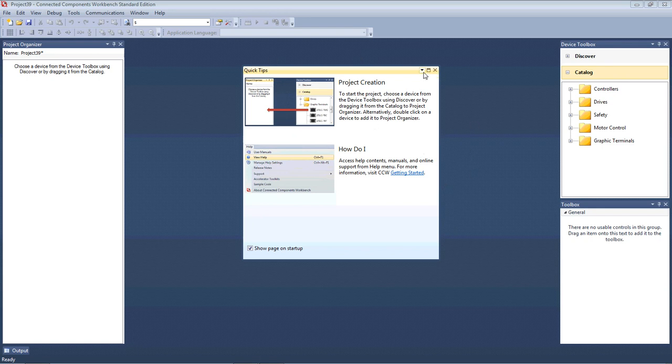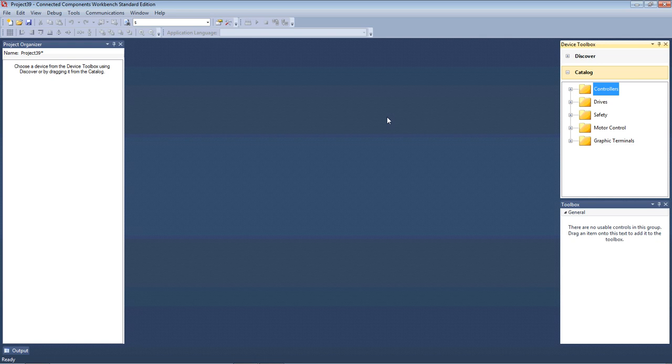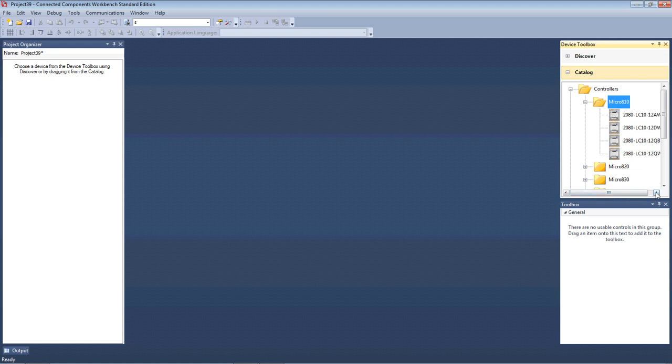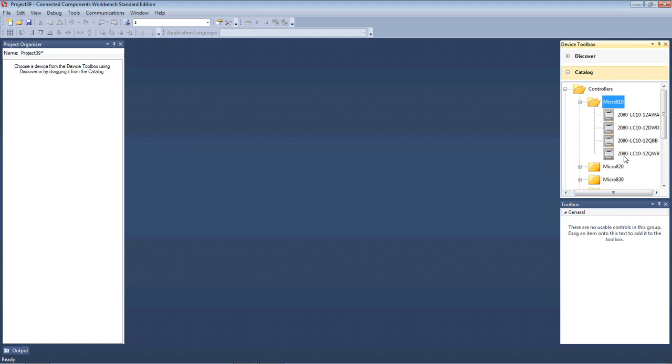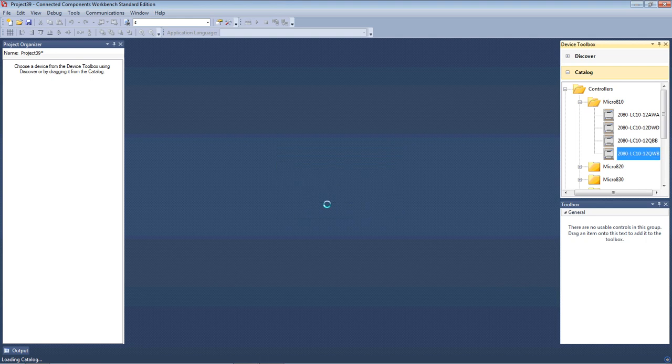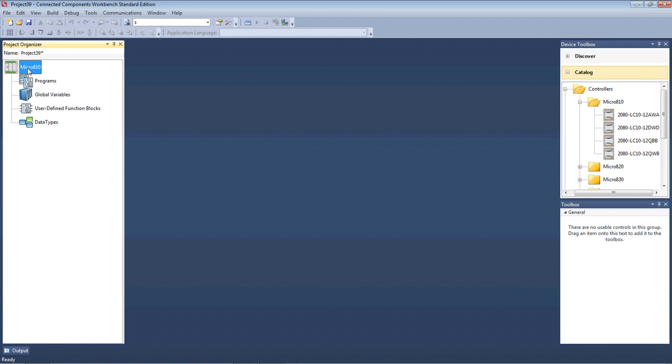I've got a quick tips page up here, I'll just close that. Now, the first thing we need to do is to tell the software what controller we're going to be connecting to via the USB cable. When I click down in the catalogue on the controllers, you're going to have a whole range of PLCs there, large, small, and what we're going to be using today, which is the Smart Relay. So, in the Micro 810 family, I select the 2080 LC1012QWB, and I drag that over, and I can drop that into the tree project organizer here. I'm going to select, go back to Major Revision 1 here, because that's how our controllers are currently set up. That drops that tree into the project organizer, so there's our project tree.